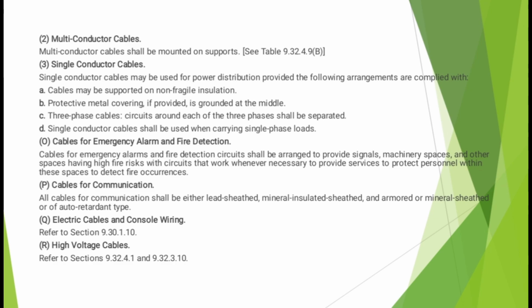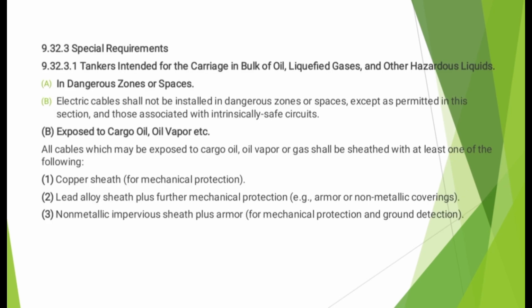Cables for emergency alarm and fire detection. Cables for emergency alarm and fire detection circuits shall be arranged to provide signal machinery spaces and other spaces having a high risk with circuit that work whenever necessary to provide services to protect personnel when these spaces detect fire occurrence. Cables for communication. All cables for communication shall be either lead sheathed, mineral insulated sheathed, or armored or mineral-sheathed, or of flame retardant type. Electric cables shall not be installed in dangerous zones or spaces, except as permitted in the section and those associated with intrinsically safe circuits.